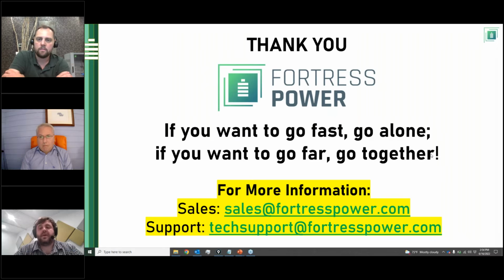There's a lot of additional performance you gain out of the battery when doing the closed loop. It's not so much about degradation of the battery at higher rates of discharge, like 1C rates instead of C/2 rates, or 1-hour discharge rates versus 2-hour discharge rates. Lithium, no matter whose battery it is, really wants a 2-hour discharge rate for maximum product life. There's no need, when the battery is below 10% state of charge, to have a 1-hour discharge rate, and no need, when the battery is at the very top of its state of charge, to have a 1-hour charge rate.